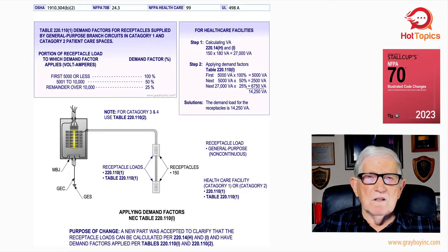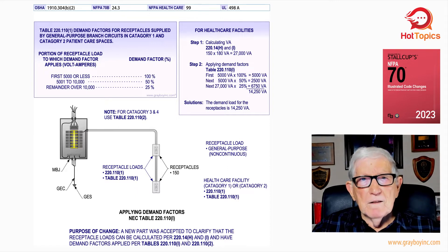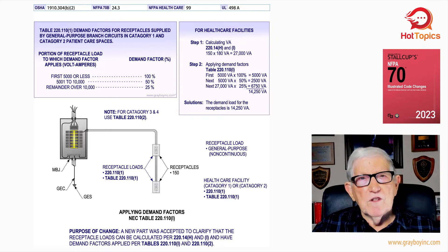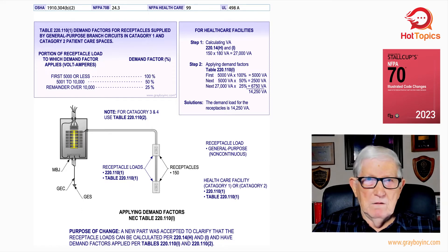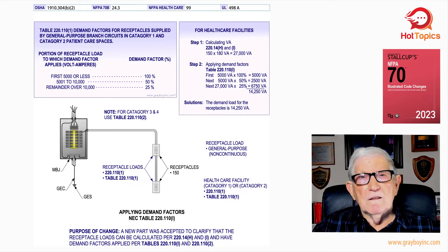That's how that demand factor is determined — through years of experience and taking demand readings and seeing how these receptacles would be used. This is basically what the rule lets you do for receptacles only, but it doesn't say anything about lighting loads. This illustration comes out of Stallcup's Illustrated Code Changes book. Looking at the purpose of the change: it's a new part accepted to clarify that receptacle loads can be calculated per Section 220.14H and I, and under certain values, you could have demand factors applied from Table 220.110.1.